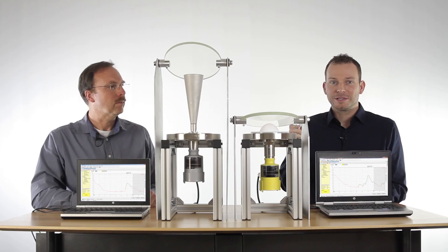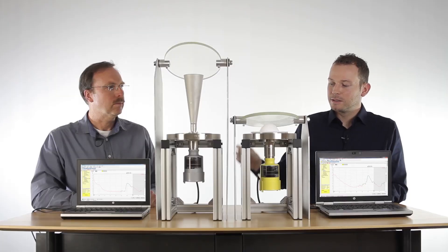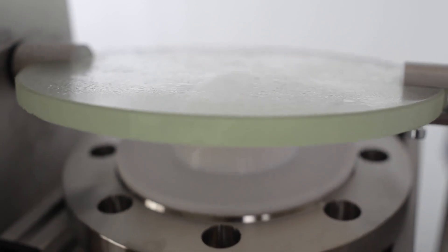What also comes up is condensate. If you have an application like this where you get condensate on the window, have a look at the echo curve - we see that there is no influence on the echo curve, so the sensor can also measure through the glass even if there's condensate on top of the glass.